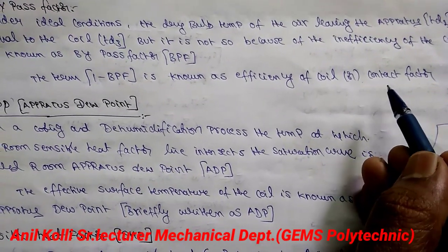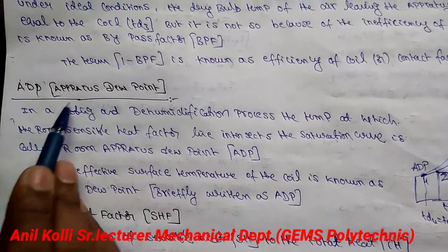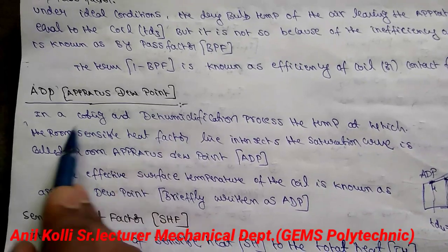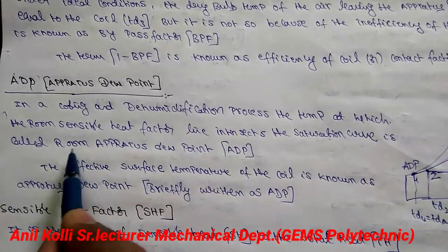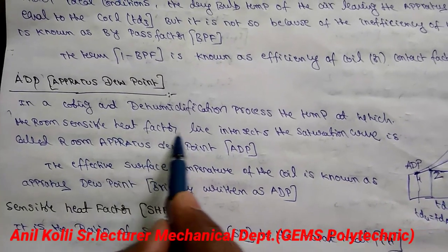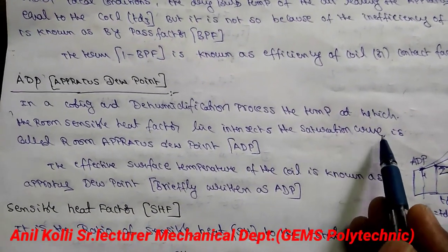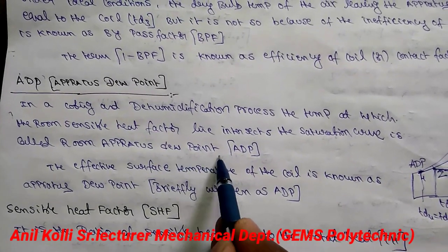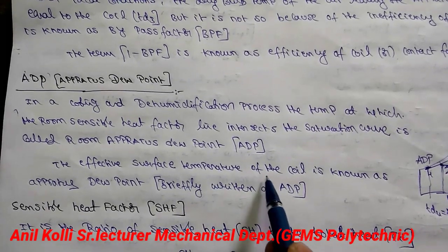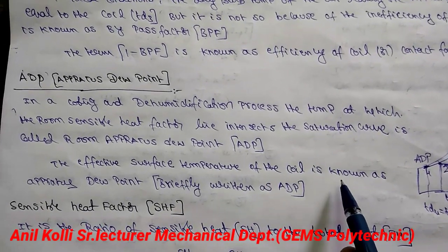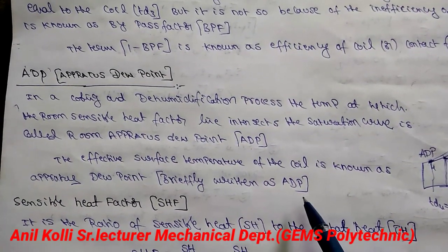Next, we go for ADP — what is apparatus dew point. In a cooling and dehumidification process, the temperature at which the room sensible heat factor line intersects the saturation curve is called the apparatus dew point. Another definition: the effective surface temperature of the coil is known as apparatus dew point, briefly written as ADP.